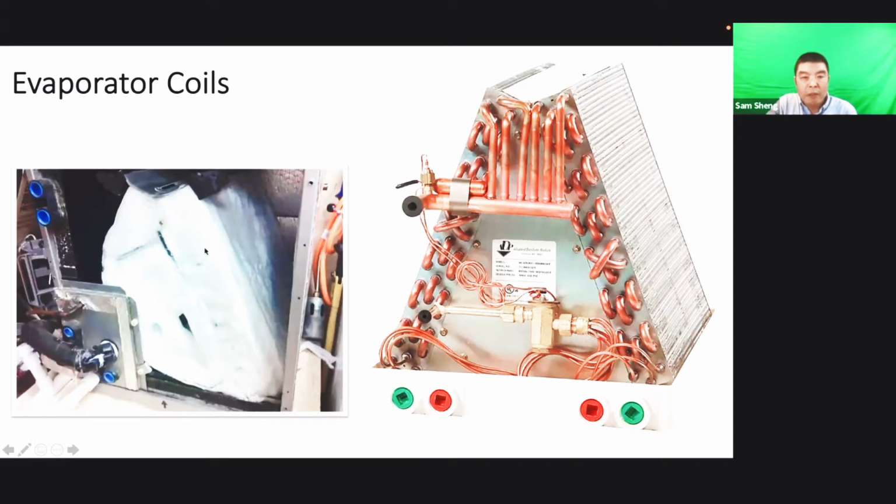That causes the same trouble as the lack of refrigerant. So that means if you see the A coil, normally you cannot see inside, but you can see here. You see this pipe connected inside to outside. You can see here is ice or frost. So that means maybe inside it's iced already. Yeah, so normally here, if you use a finger to touch, there should be condensate water here. So that's why we need to cover the insulation. We don't want the condensate water to drip everywhere. So that's why we insulate the pipe.